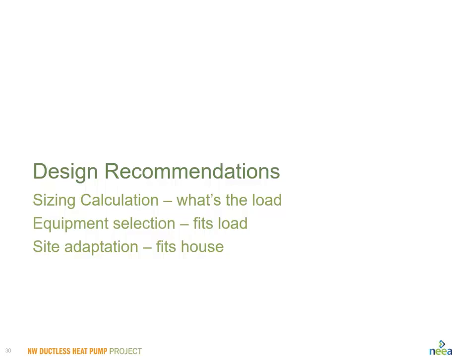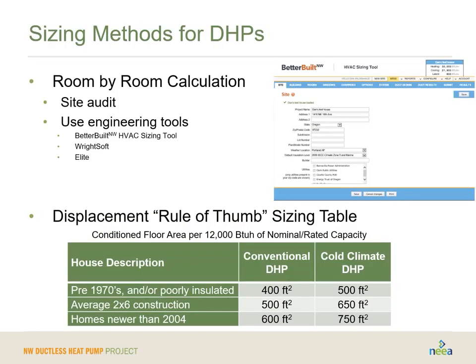So how do we take this, what we've learned about displacement and about design capacity and design loads, and how do we translate this into recommendations for design? Well, let's go through a couple of things: sizing calculation, then equipment selection, and then making sure that all of this fits the house at the right size. The first thing we want to think about is sizing these. There's a couple of things. The first is, in more complex homes and homes that may have more than one ductless heat pump head going into them, so even though our displacement looks at one, you may have a homeowner who also wants a head in their bedroom or something like that.